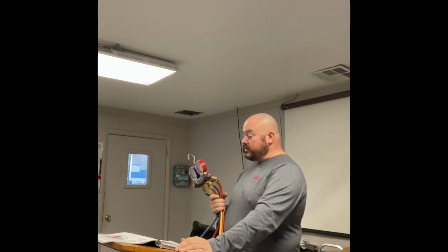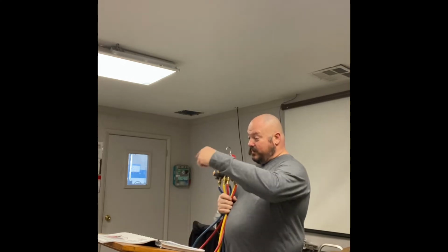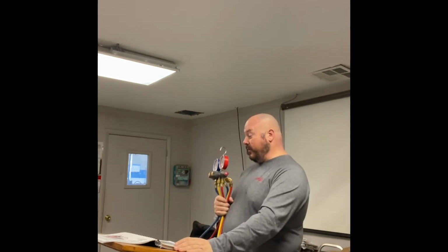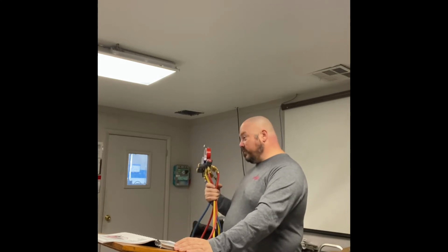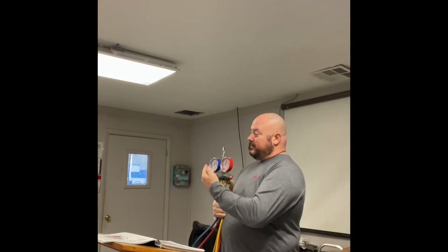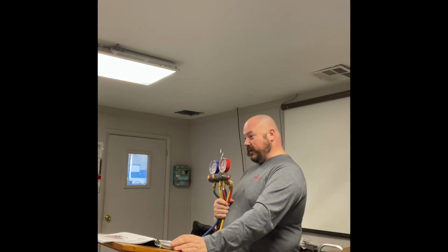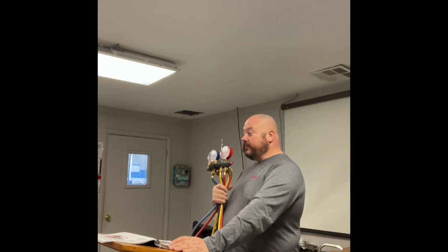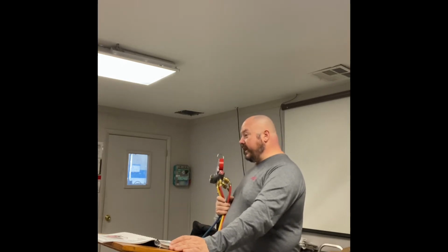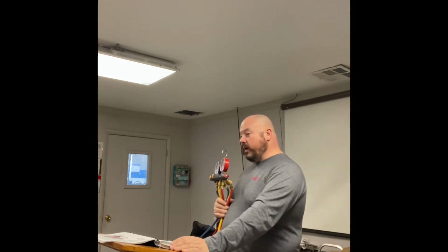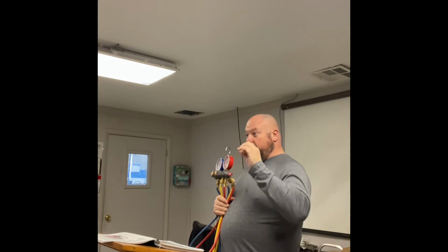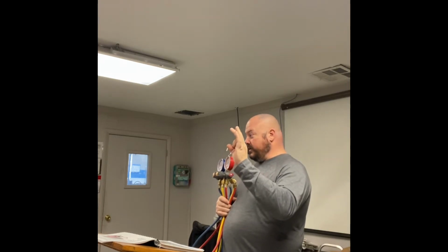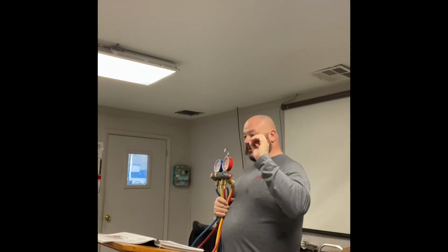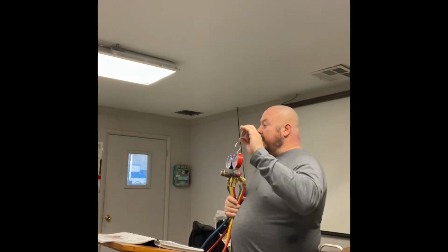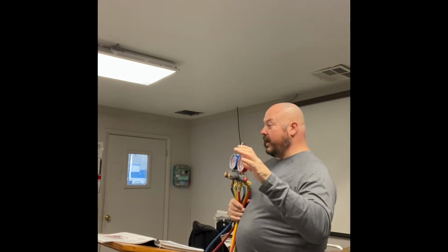Remember, your suction side is the largest tube, which is the hardest to solder, which is the one that you should solder first, because then you can get all the way around it without having that little liquid line in the way. Then what's probably going to happen is on the bottom side of that, where you're having to stand on your head, lay in the mud while it's raining, and some dog's biting in the nuts, that's probably where your leak is. If it's not there, it'll probably be at the coil on the inside, and right there where you bolted it onto the TXV or the metering device, there's that little O-ring. If you don't have that tight enough, start there, backtrack from there.